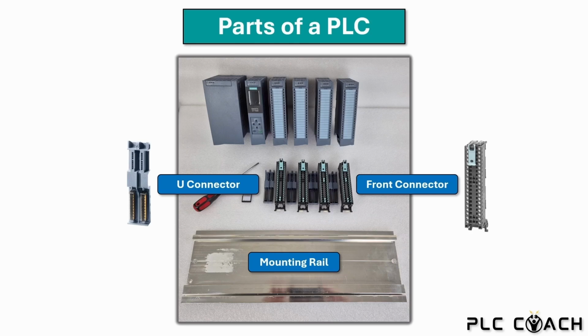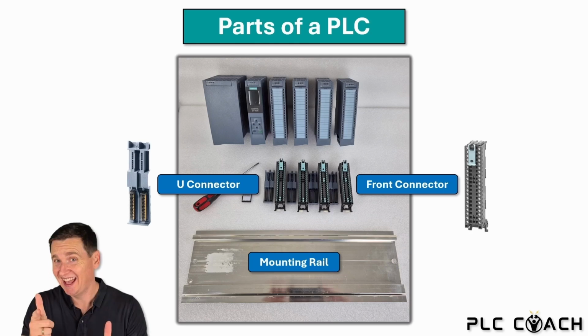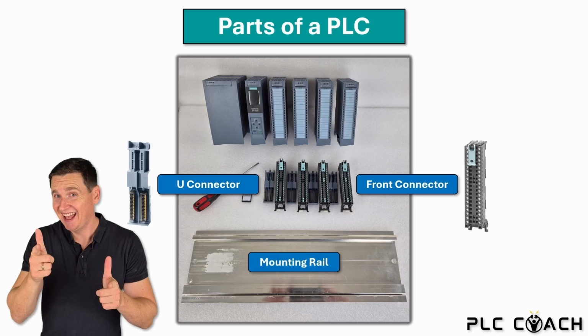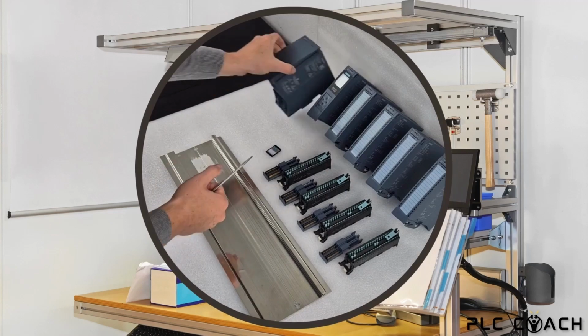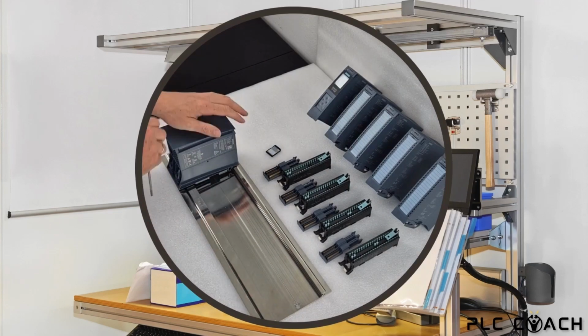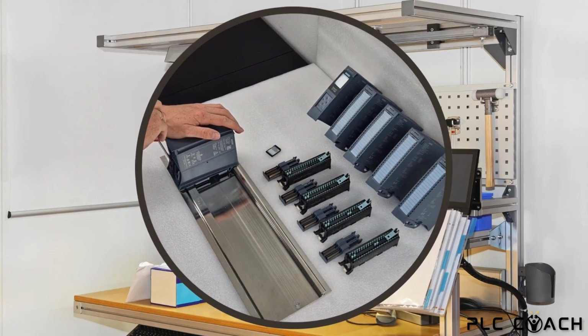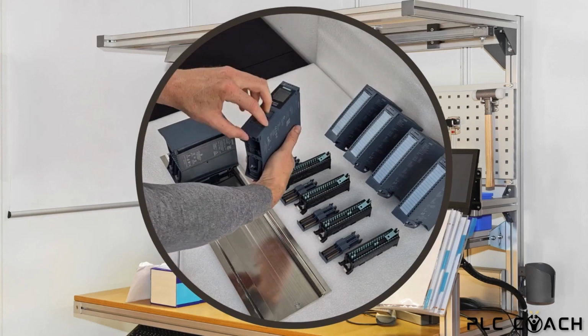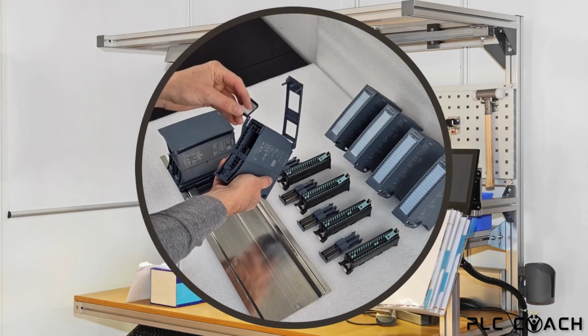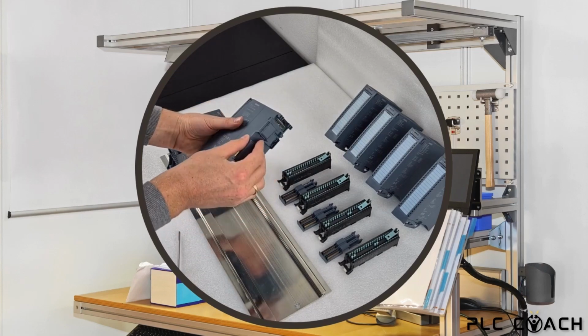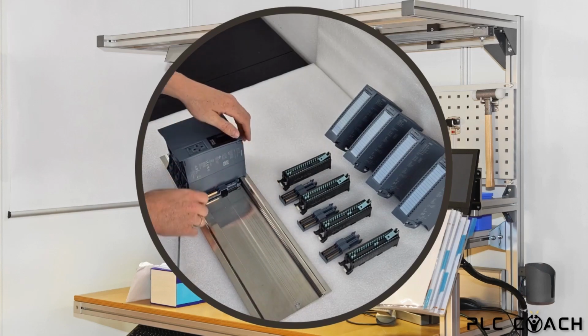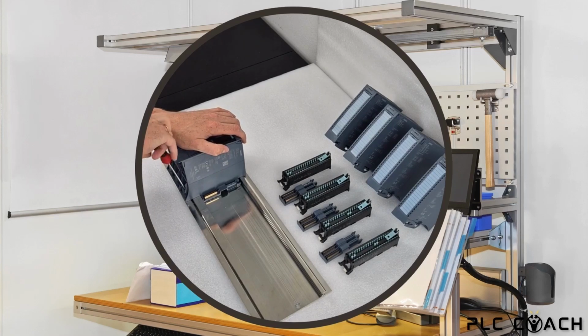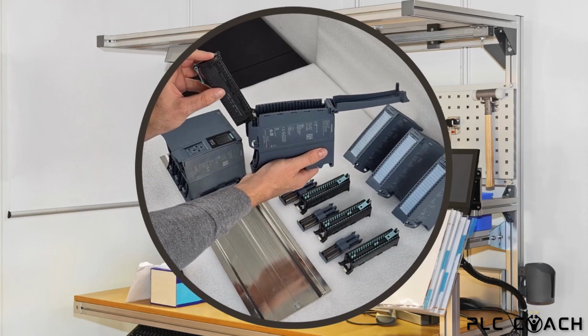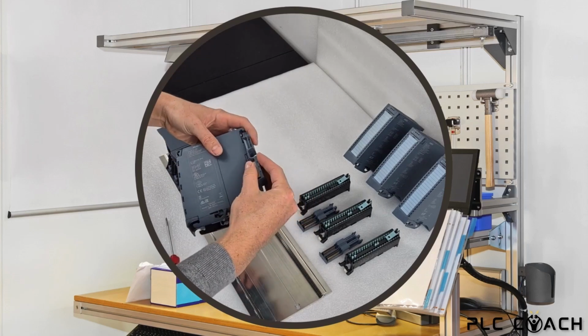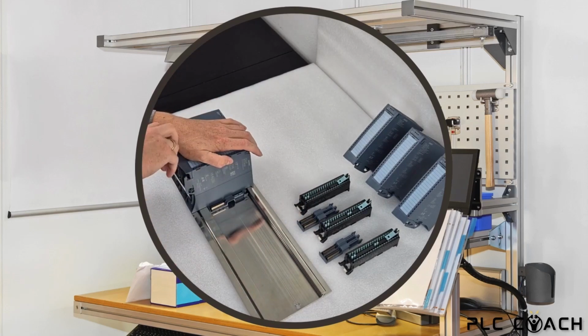And now guys, you have some time to relax. You can watch me for a few seconds as I assemble the PLC. Let's go to the workbench. First, I install the power supply. The S7-1500 requires a memory card. The U connector ensures data exchange between the modules. We can connect the cables of the sensors and actuators to the front connectors of the input and output cards.